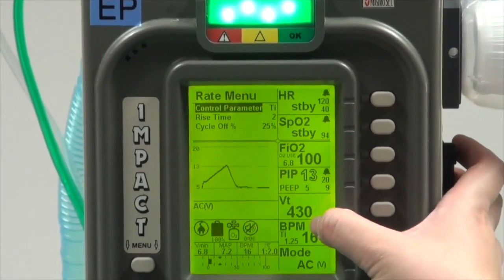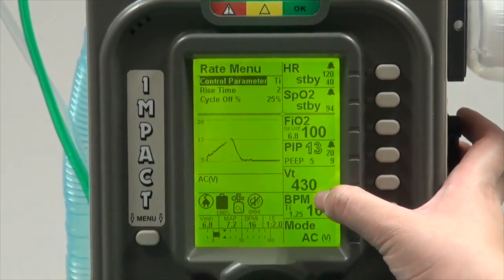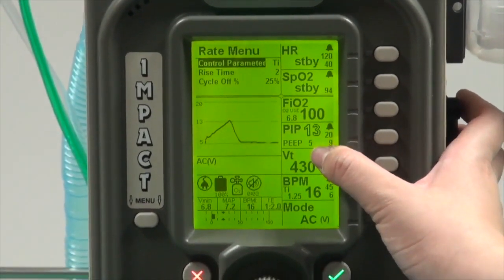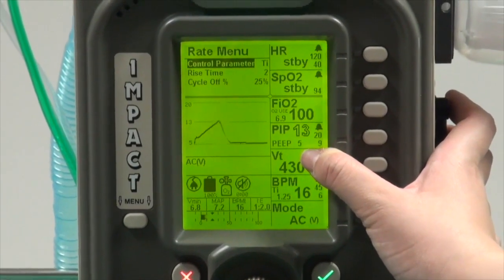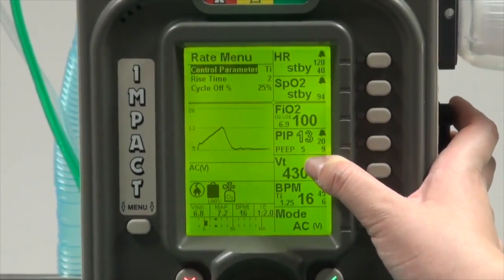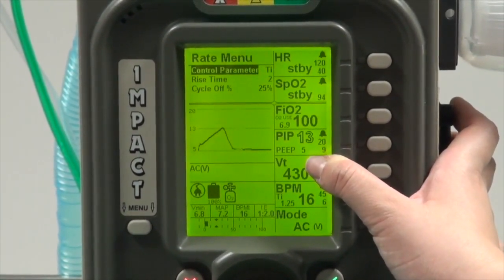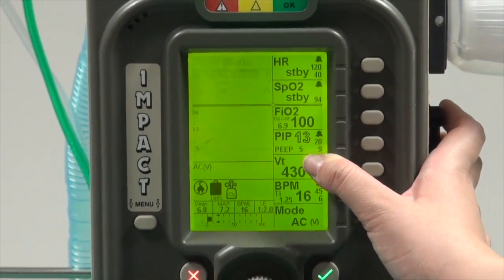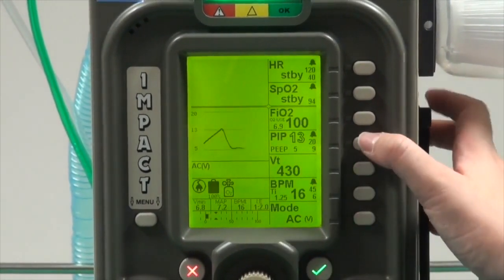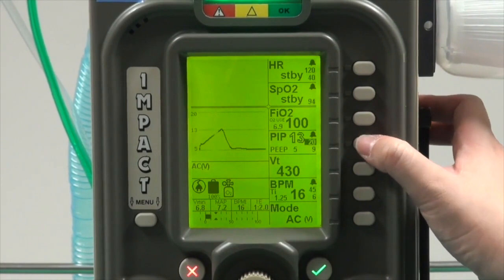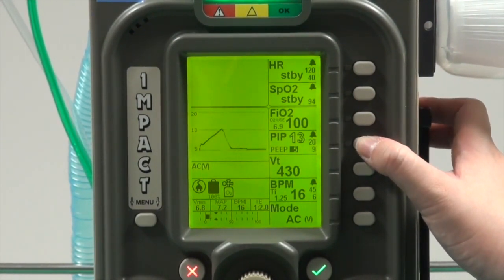This is our tidal volume that we're going to deliver to the patient. In this pressure window, notice that the PIP, peak inspiratory pressure, is a hollowed out number. This means that it's a measured value instead of a setting. Notice when I press the button, I'm unable to choose it at all. The PIP is a measured value.